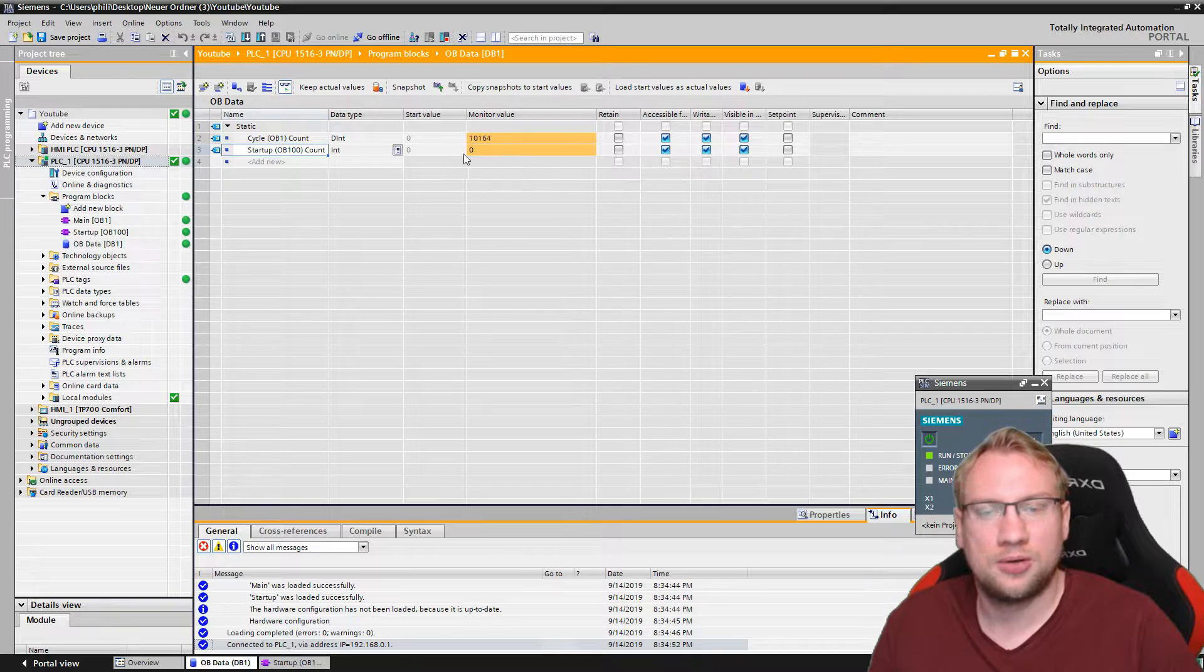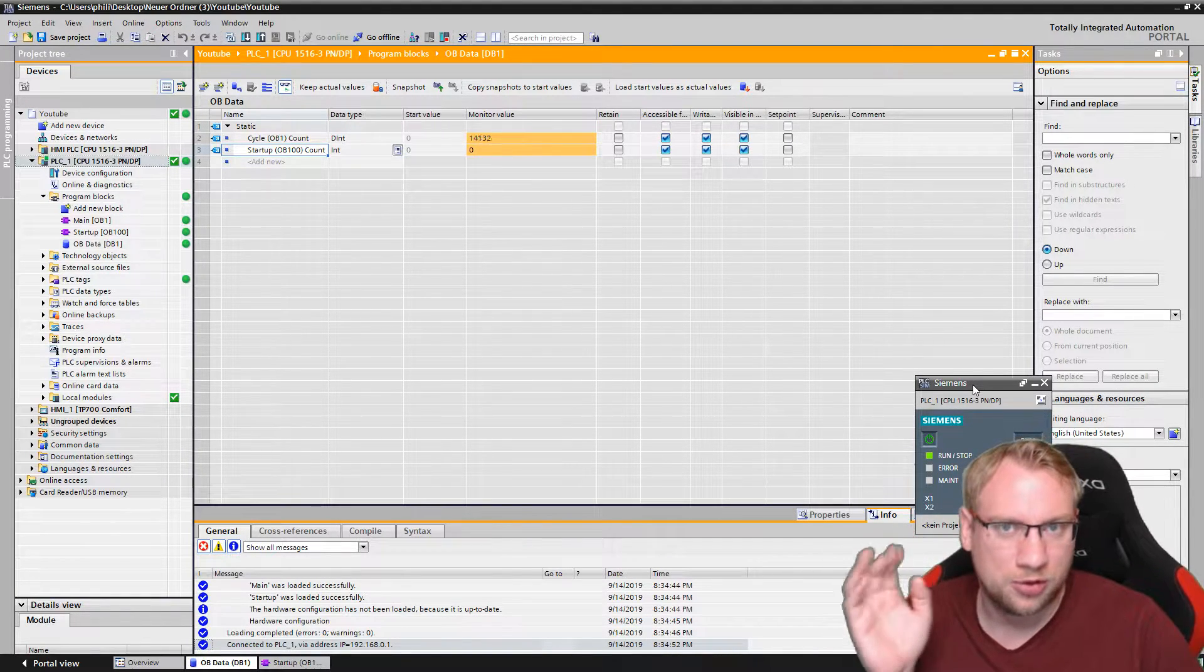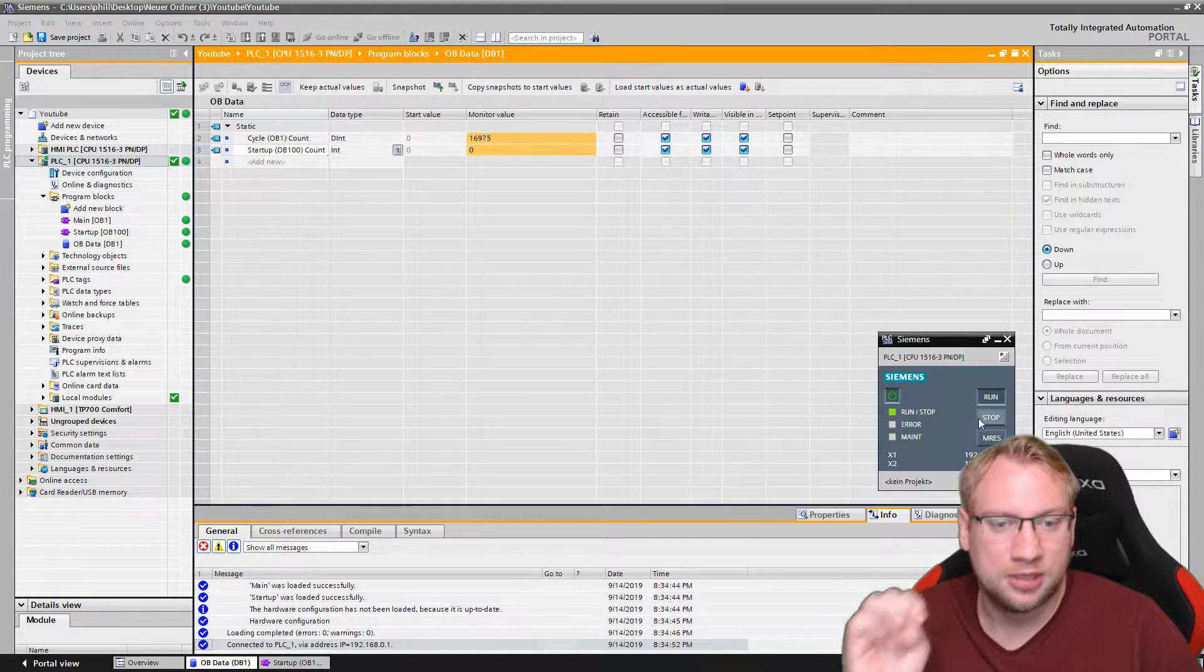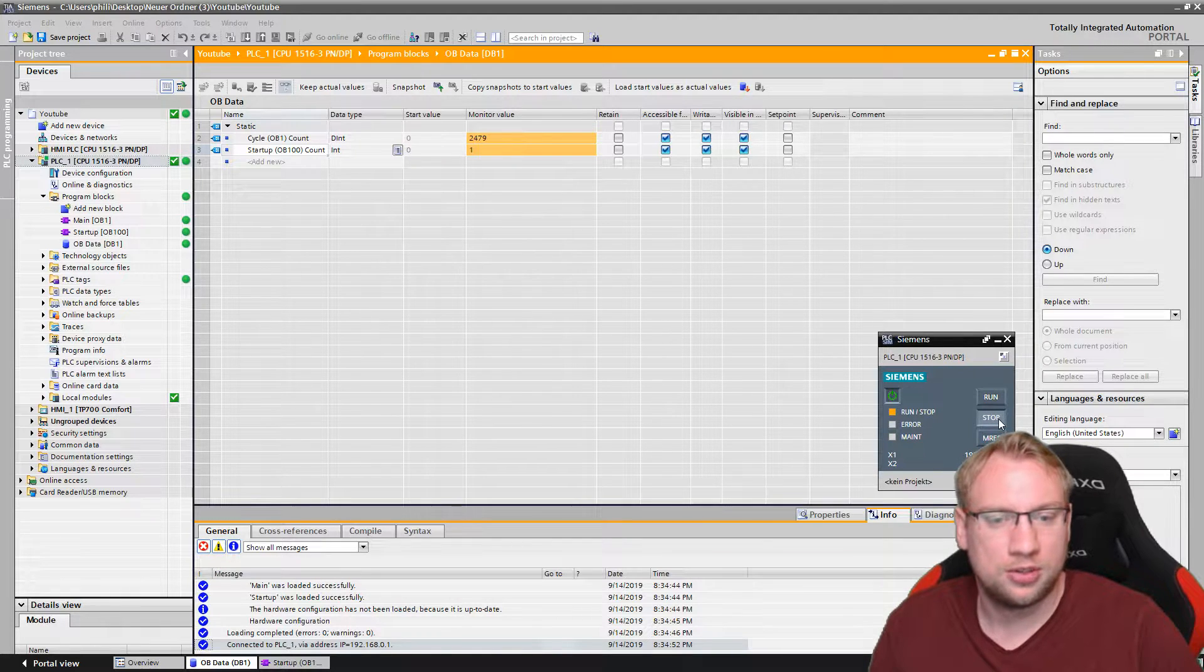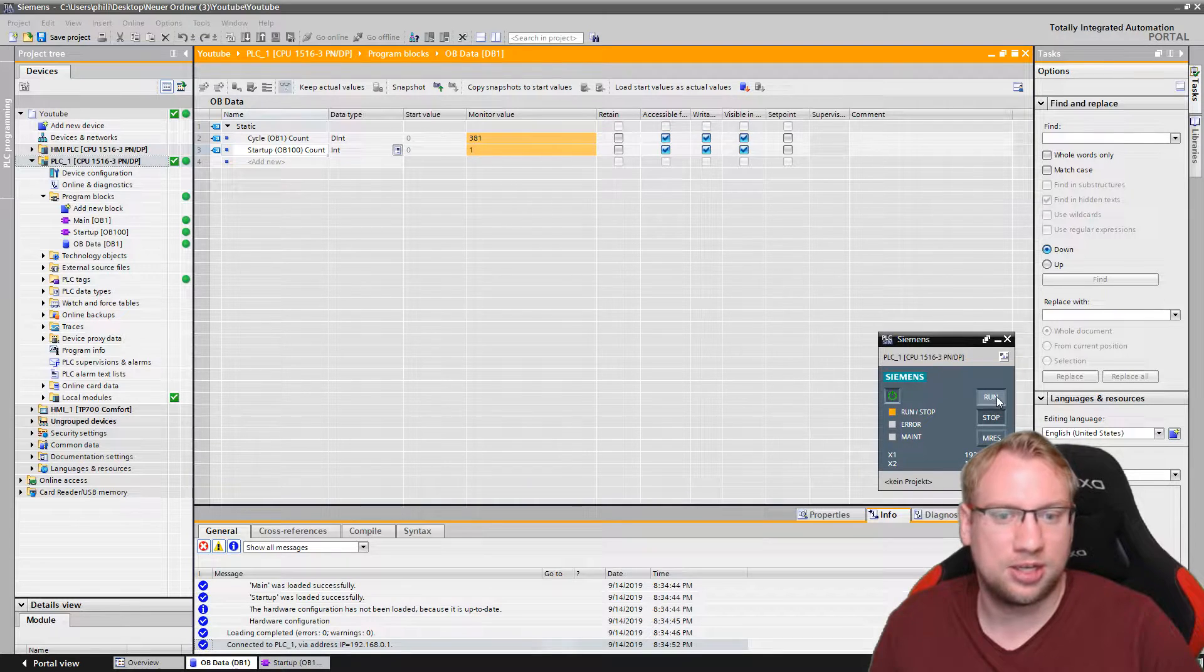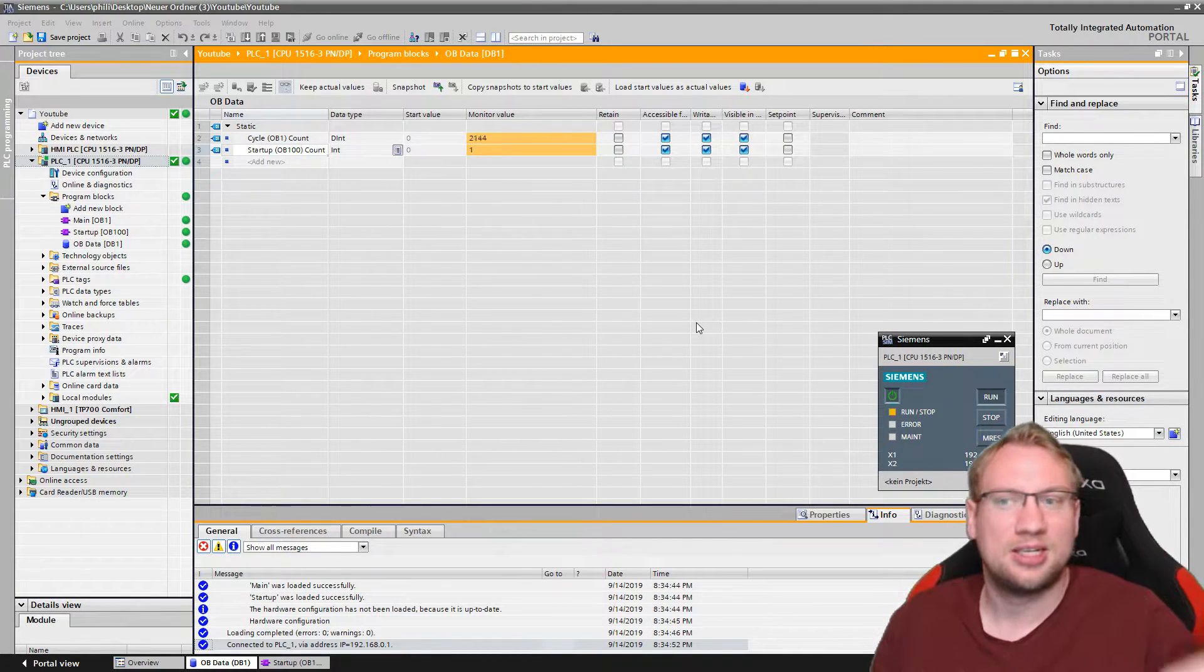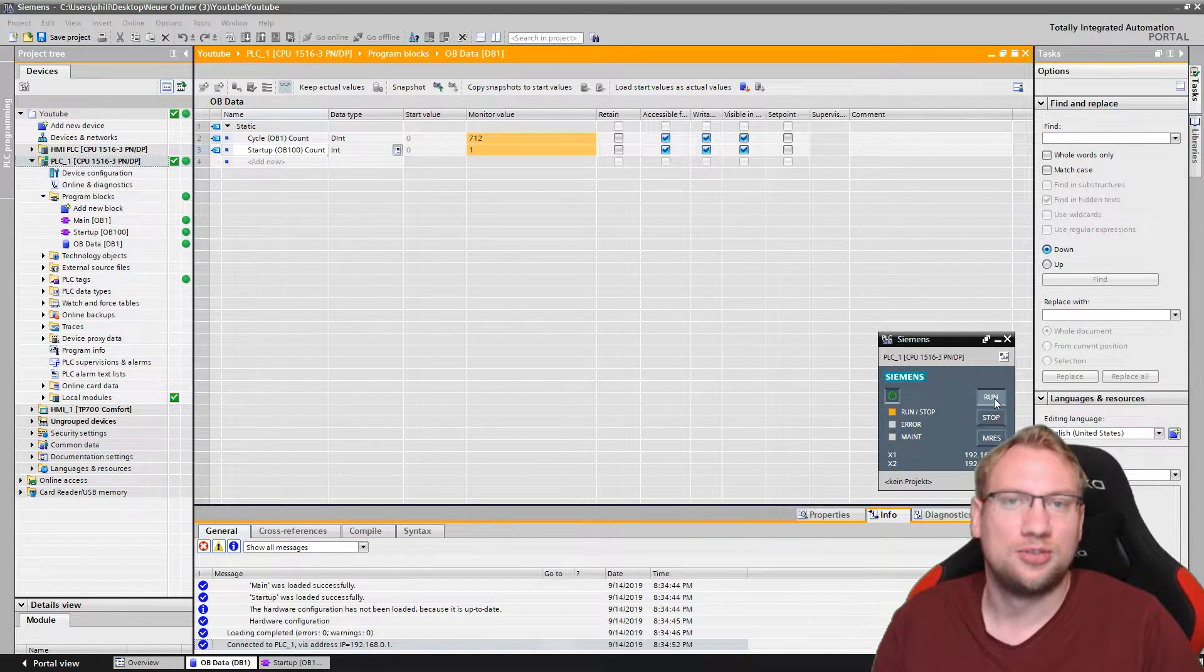So right now you see the counter is at zero because my PLC has not restarted. If you download the program, the PLC does not restart. If I now do stop and run, you will see the counter is one. If I do stop and run again, it's still at one. It doesn't change anything because every time the PLC starts, you see it with the cyclic counter, it's actually resetting to zero.